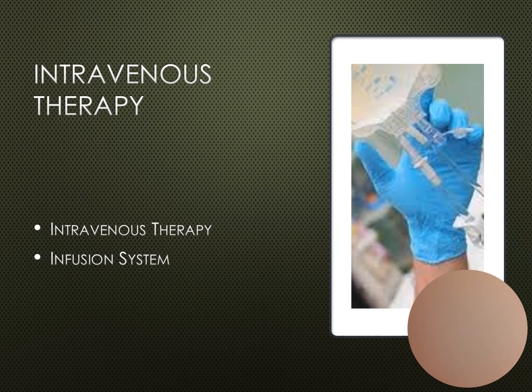Some of our add-on devices might include those extension sets, filters, or stopcocks. The extension sets are often used for extra length in the IV administration set. Stopcocks are used for administration of intermittent fluids or medications through an administration set. Basically what it does is directs flow of one solution or medication to the IV access device while shutting off flow to the main solution. We frequently see this in the operating room, critical care, or trauma settings.